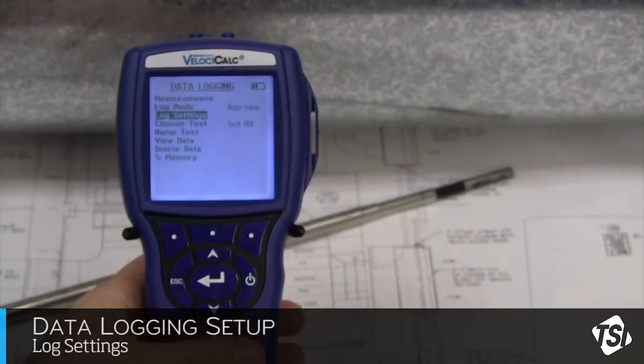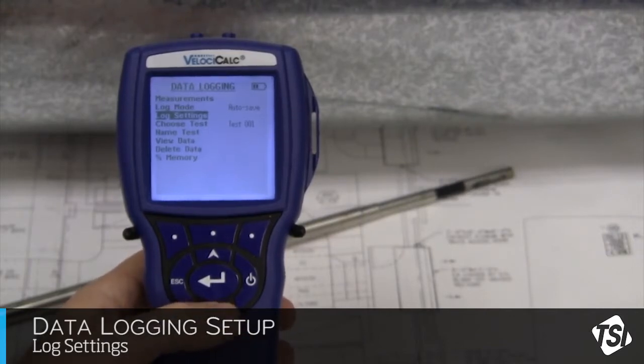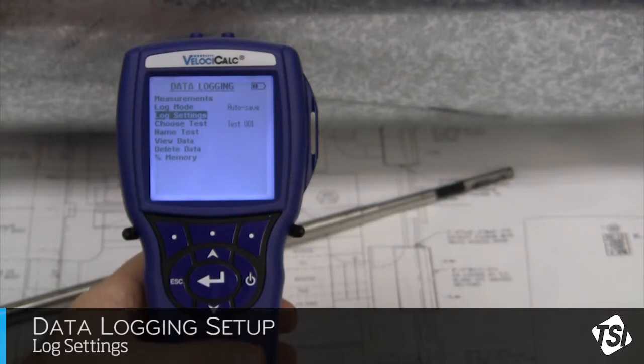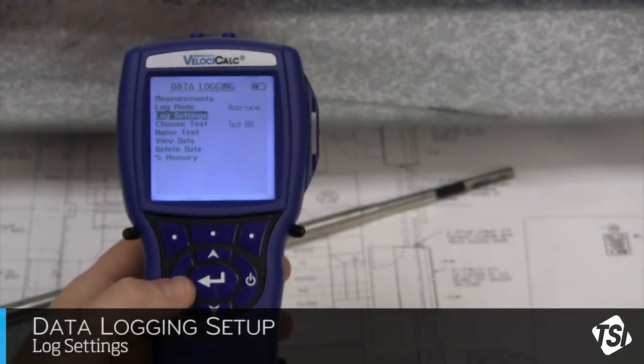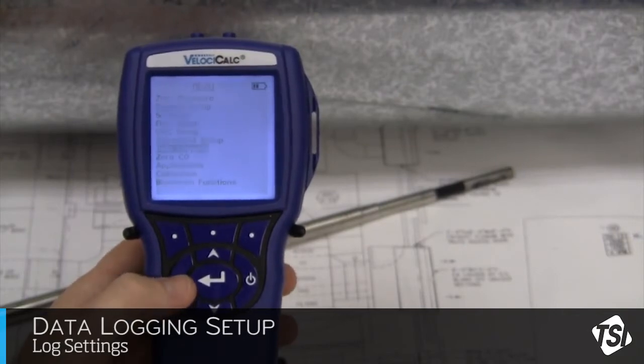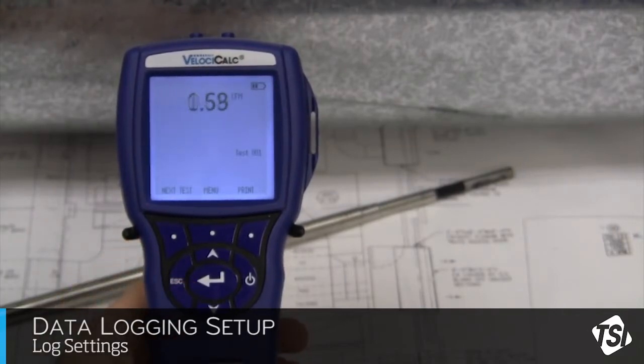At this point, you will want to note what test number has been selected. Each duct traverse performed should be saved under a different test number. In this case, the test is 001. Each sample taken in our duct traverse will fall under one test number. Press Escape to return to the main menu and Escape again to get back to the main screen where our measurements will be displayed. We are now ready to take our readings.